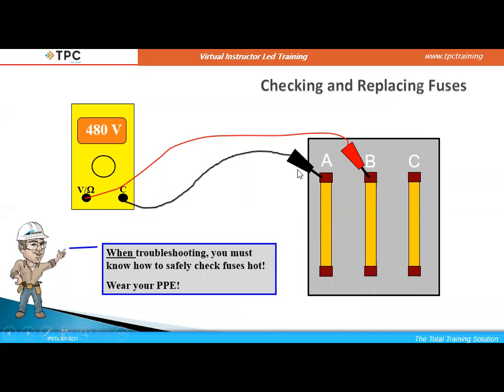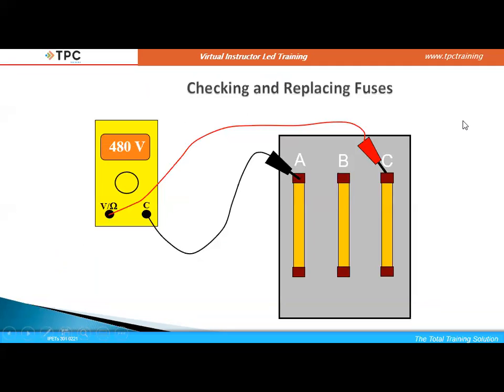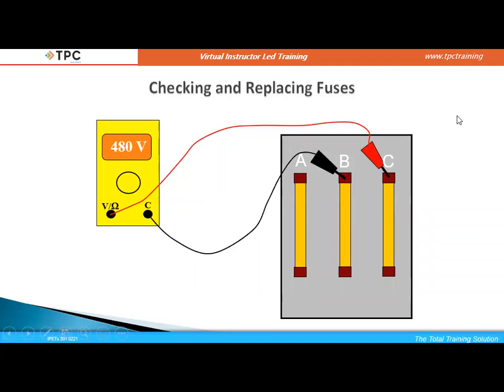Now, if we want to check these for whatever reason while they're energized, OSHA gives us only one method to do this, and they call this the crisscross method. There are times when I just can't de-energize and I have to troubleshoot a little bit. Right now, I'm not checking any fuse. I'm just verifying that I have my incoming power to the line side of my fuses. Between A and B, I have 480. Between A and C, I have 480. And B and C, I have 480. So I see that I have the proper voltage on the line side of my fuse.